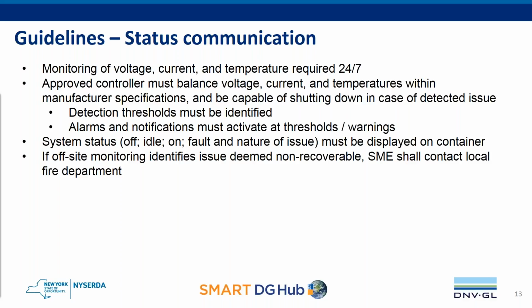If the system goes outside of those safe ranges, you must be capable of shutting down the system in case of that. So you have to identify detection thresholds and have alarms and notifications to activate at those thresholds or warnings. And then not just alarms and notifications, but also the ability to automatically stop. The system status should be displayed visibly on the unit. So this can be something as simple as a small LED indicator of various colors to indicate if it's on or off, idle, fault, etc., or a small screen.